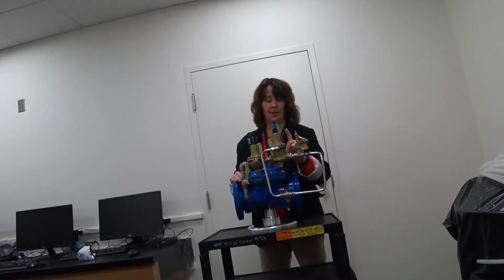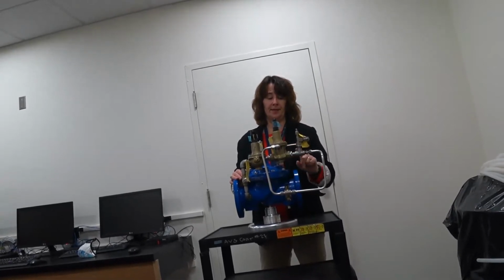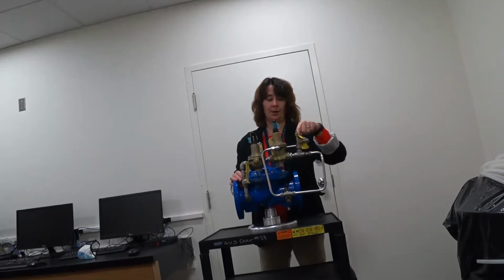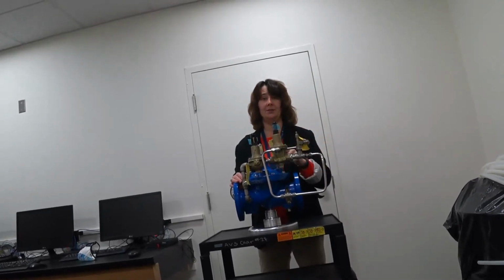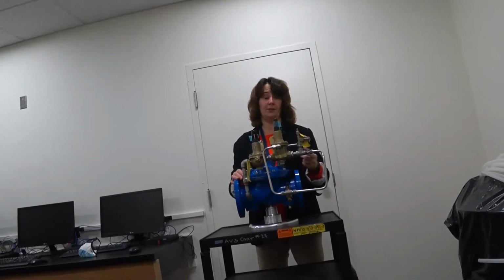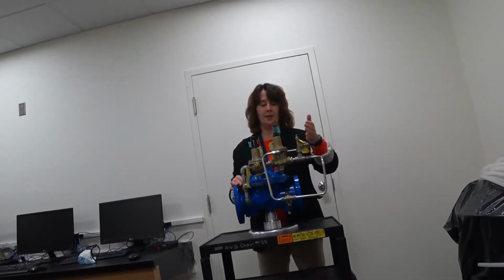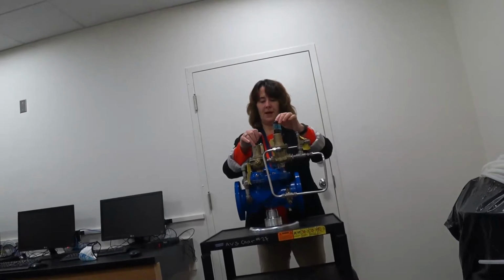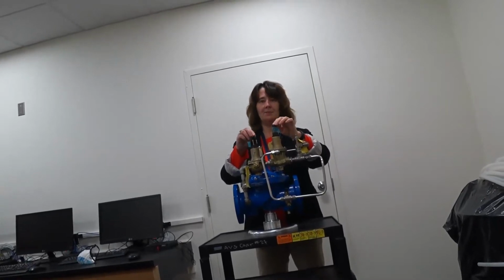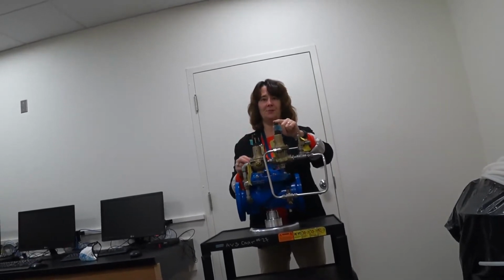Now, if this valve here is closed, it's going to force that 0.1 gallons per minute onto the top of the bonnet, all of it. You don't have a choice. You're going to go on here, okay? Now, this second valve here, it doesn't matter whether it's opened or closed if this one's closed.